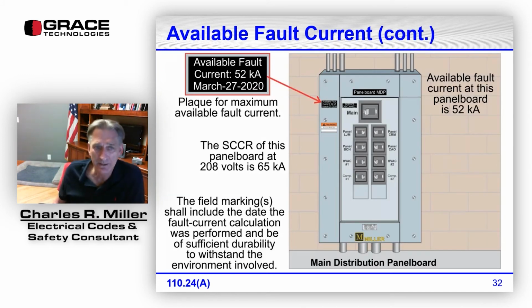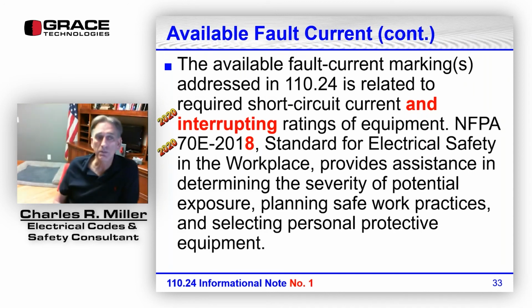Here's an illustration showing this. On my switchboard here, I've got the available fault current at 52,000 amps. The date was on here, in case you're interested, that date, not the year, but the date, March 27, is our anniversary. So it has a plaque showing the available fault current. The short circuit current rating of that panel board is 65,000, and has to be at least equal to or above the available fault current. And the marking has to include, which it does, the date the fault current calculation was performed, and has to be of sufficient durability to withstand the environment. The available fault current markings addressed in 110.24 relate to required short circuit current and interrupting ratings of equipment.